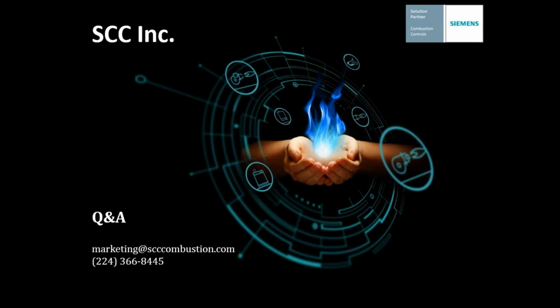That's a very common question. The LMV5 was the initial linkageless flame safeguard series that Siemens released. The LMV3 was added later, about 5 years after the LMV5, as a lower cost alternative for the smaller burners, so that we could add linkageless economically to smaller burners as well. So the LMV3 only has 2 active servos. You need an LMV5 to do 3 or more servos at the same time, such as FGR, secondary air, or secondary gas. You also need the LMV5 whenever you do oxygen trim, because the oxygen trim module is only applicable to the LMV5. It's on the CAN bus system. So the LMV3 is a lower cost alternative, has less capabilities, but it's still a linkageless control used on small burners, and its intent is to be an economical approach to a smaller burner. LMV5 has higher torque actuators as well, all the way up to the SQM9. LMV3 has smaller servos, as it's intended for the smaller burners.